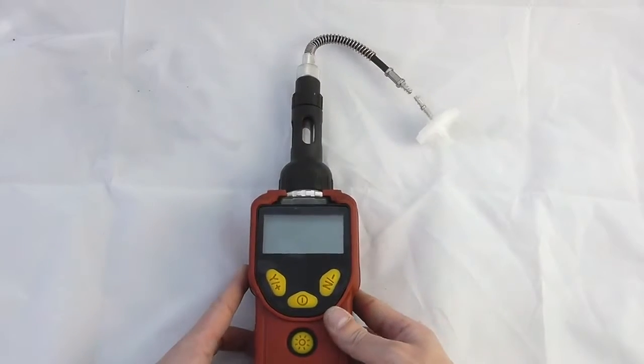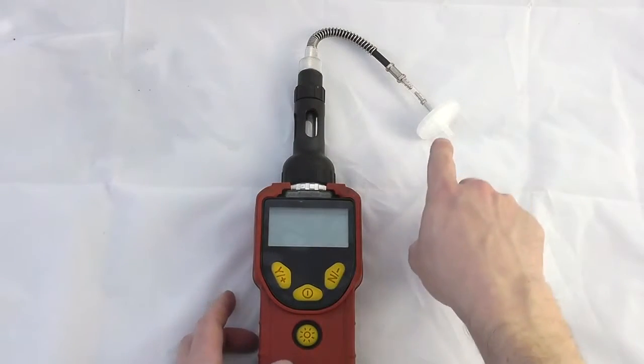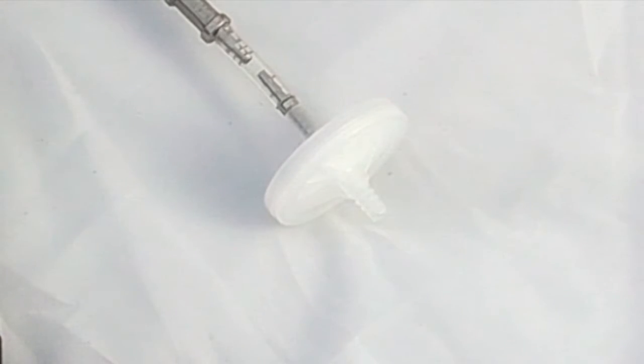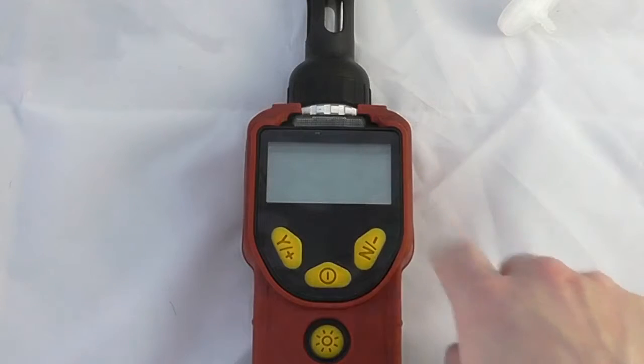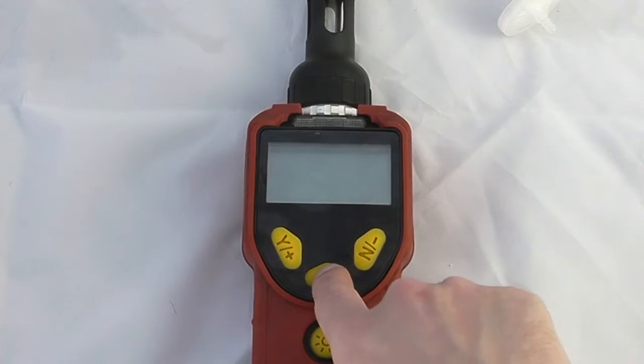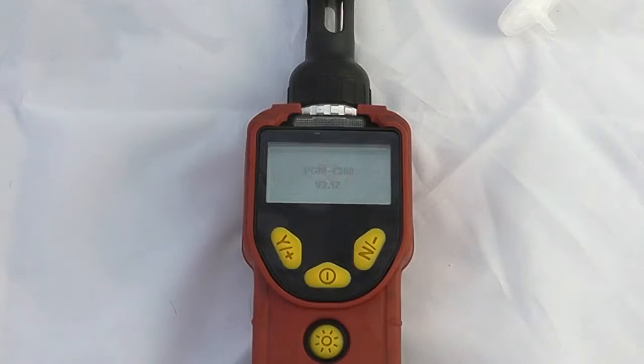It is important to always operate with a hydrophobic filter. RAE also do a line of humidity filtering tubes which may be appropriate in higher humidity environments. So operationally speaking, we start the instrument up using the on-off button, and then the instrument will go through its startup procedure. It'll do a few tests on the unit itself and then go for our lamp option.